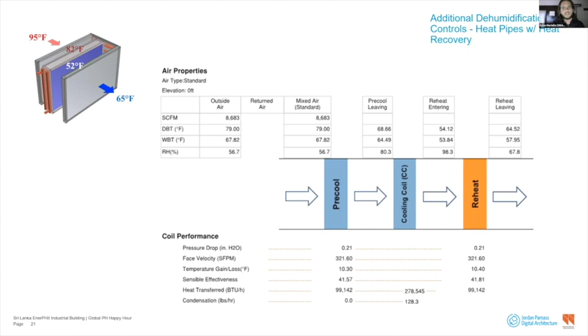There's a heat pipe that absorbs heat from the incoming air that's already hot and warm, and it takes that heat and moves it over here after the coil. And once that air gets not only cooled, but also super cooled down to that temperature where they can condense all that moisture out, now we're just using that recovered heat that was, quite literally, wrapped around the primary cooling coil to reheat it. And that provides a significant savings for the project. Next slide.